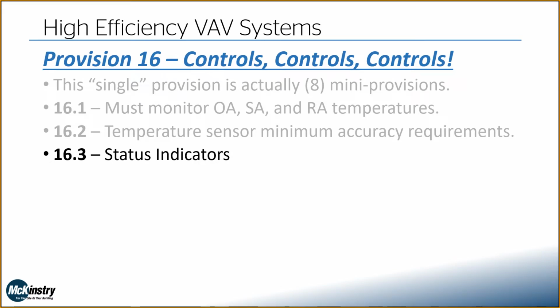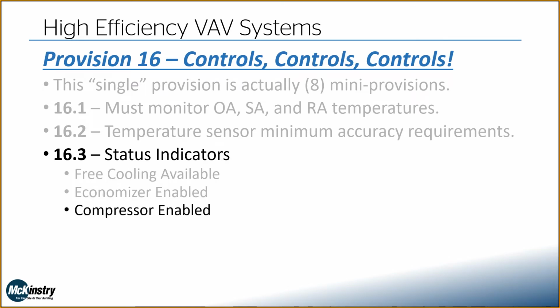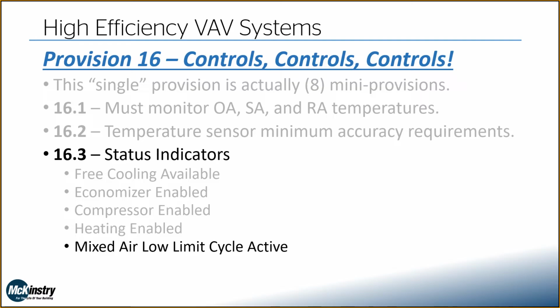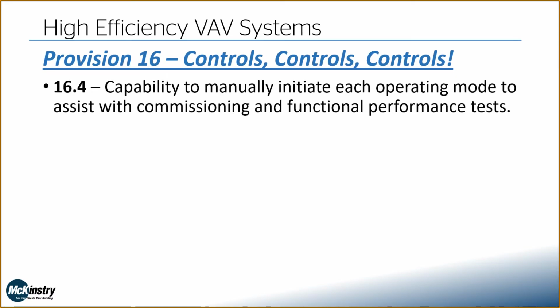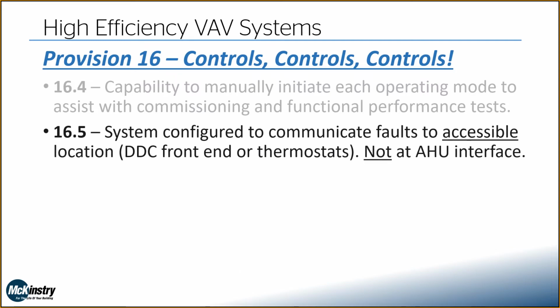We have to have a number of status indicators. Free cooling is available. Economizer is on. Compressor's on. Heating's on. Our mixed air low limit cycle is active. And the current value of each sensor. We have to have the capability to manually initiate each operating mode to assist with CX and FPTs. So our commissioning team, if they need to simulate economizer operation, or reset strategies, or anything, really, they have to have that capability to manually initiate them.